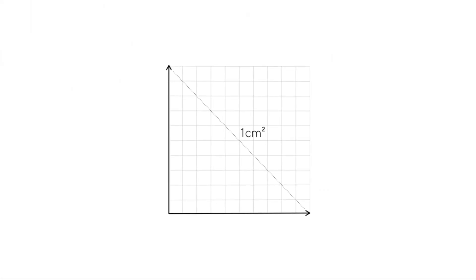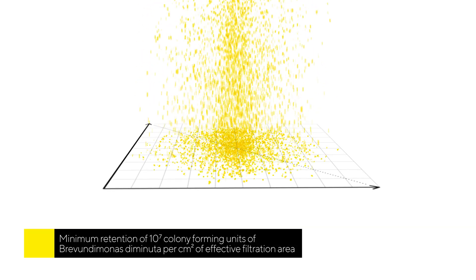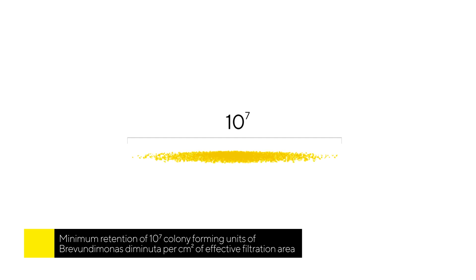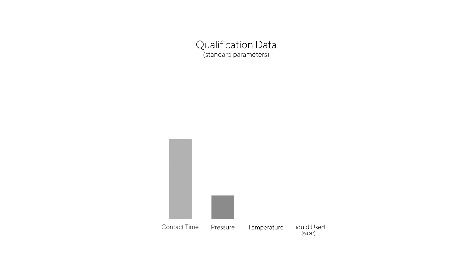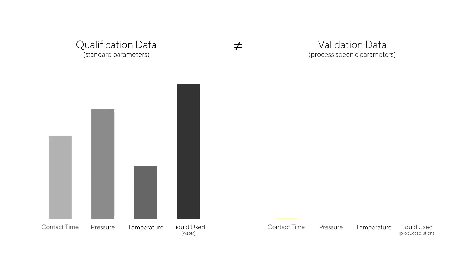Sterilising grade filters have to retain a minimum of 10 to the 7 colony-forming units of Brevundimonas diminuta per square centimetre of effective filtration area. Qualification data determined under standard conditions is not sufficient to guarantee sterilising grade in production. Consequently, regulatory bodies demand validation data determined by a process-specific bacteria challenge test.